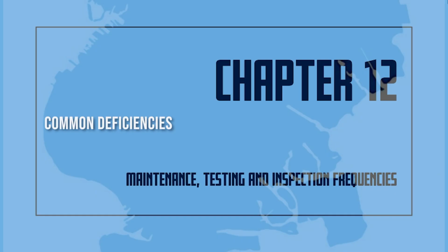The certificate of fitness holder shall assume that the system being inspected is installed in accordance with the New York City Building Code in effect at the time of installation. The certificate of fitness holder is to report those items of change that impact the system components regarding compliance with any retroactive requirements, the condition of the water supply control valves, water and air levels in reserve tanks and condition of same, unusual changes in water supply or system pressures, condition and accessibility of control valves, fire department connections, clearance around sprinkler heads, accessibility of curb valve box, system control valves, required signage, attachments to piping other than system components, misaligned piping due to impact, missing pipe hangers and supports, excessive operation of pressure relief valves, easily recognized recalled sprinkler heads, and visible leakage. Factors that may require further investigation.